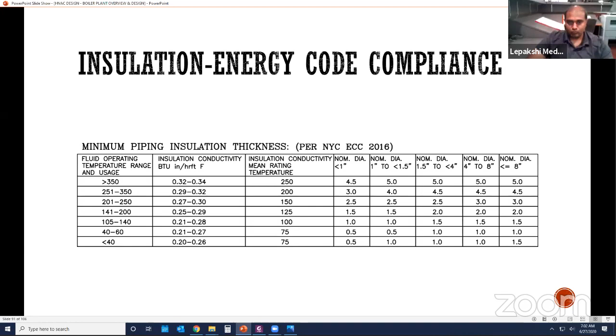For instance, let's talk about steam. In low pressure boilers, the steam temperature will normally be in the range of 251 to 350 degrees. So the insulation thickness has to be this size. You have to pick and choose the insulation for your system so that you can reduce the heat wastefully going out. But you have to design everything as per the codes, whatever it complies to.